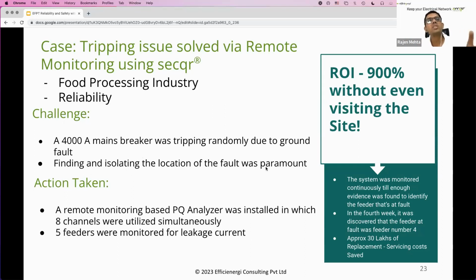Finding and isolating the location of the fault was very important, because it was causing the entire plant to have an impact on the production. So what, as I mentioned, we did is we deployed this remote monitoring power quality analyzer, and 8 channels we utilized simultaneously. Without even visiting the site, we could find out the root cause of the problem.